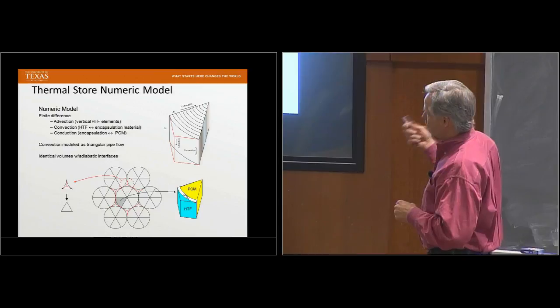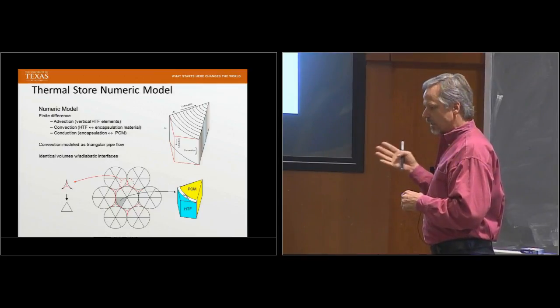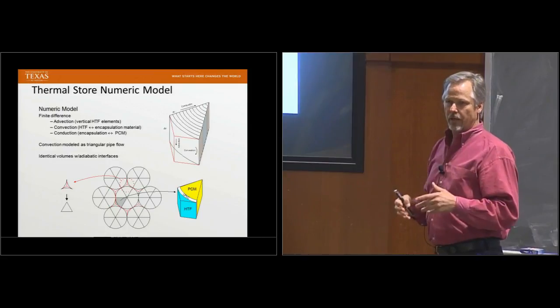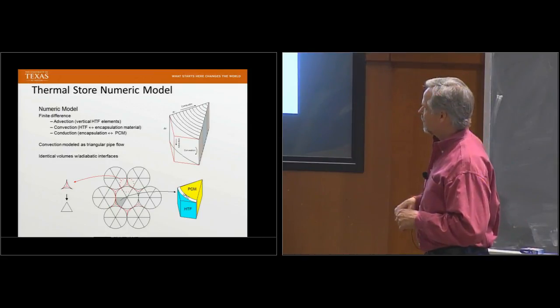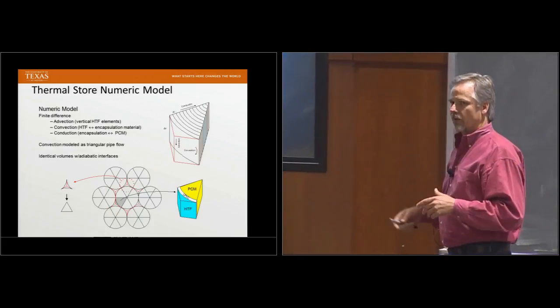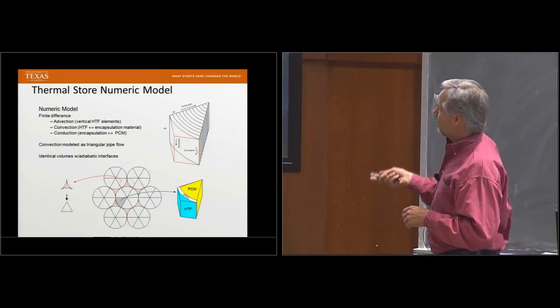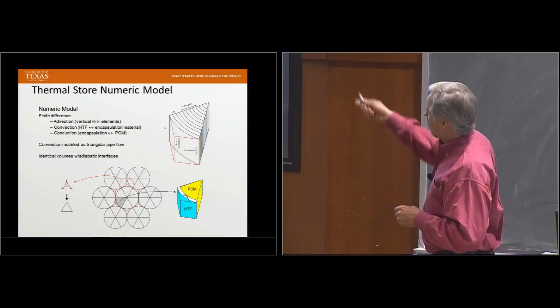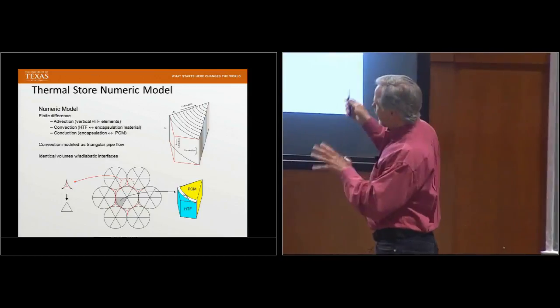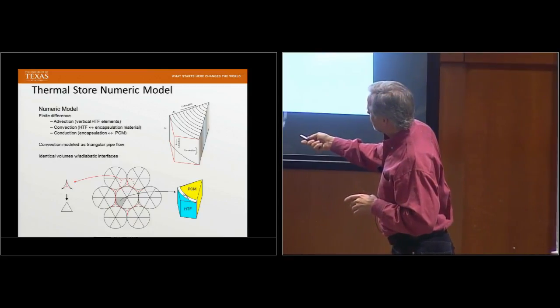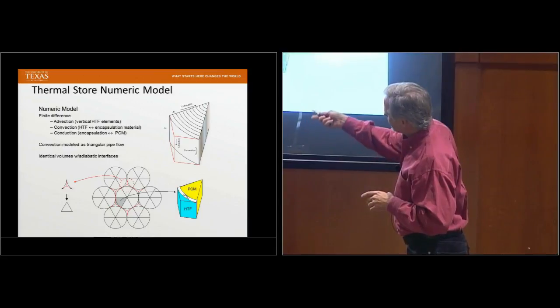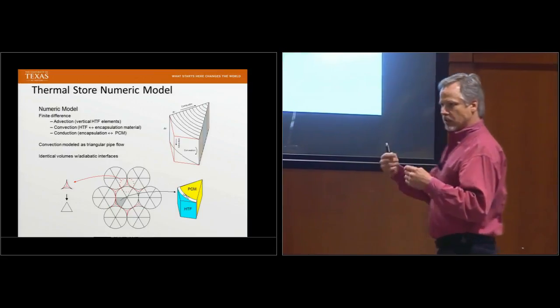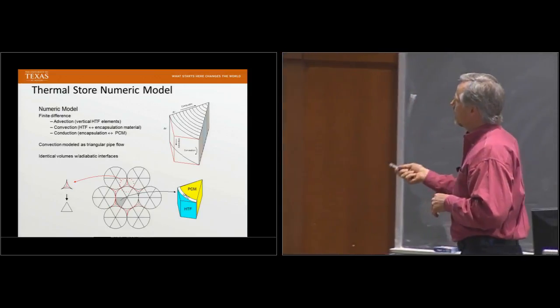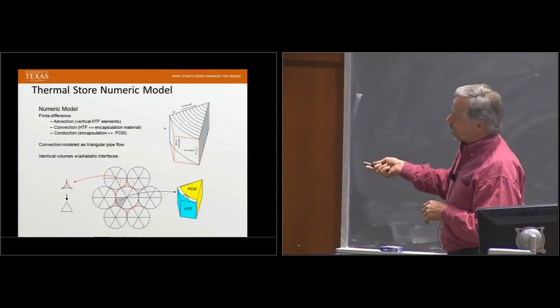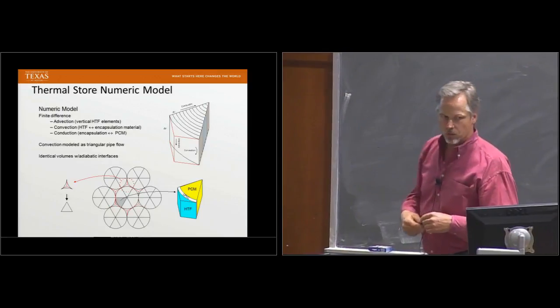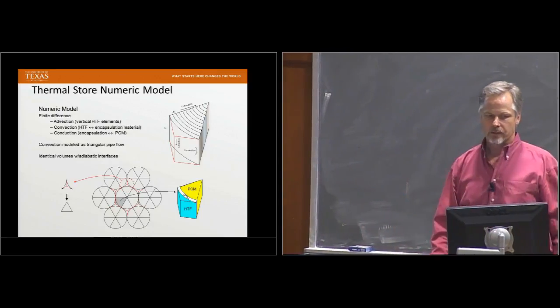It turns out, when we get to the model, you'll see that this particular design is not convection limited, it's conduction limited. So we can change the convection coefficient dramatically and have very little effect. But this looks like it works pretty well, and I'm hoping to validate it when we do the physical model. By doing this particular design, we end up with these diamond-shaped units that are all identical. The interfaces drawn in red there are adiabatic interfaces. They're all the same. We're not going to have any heat transfer across them. So we really only need to look at this one element and then multiply it by 6 and by the number of tubes, and we get our total thermal performance capacity.